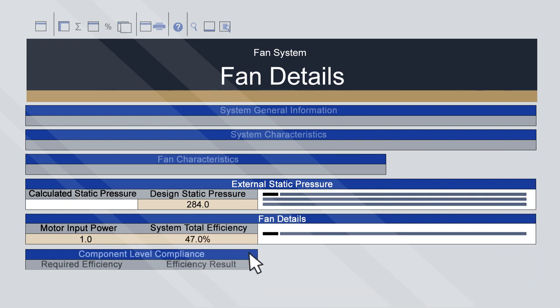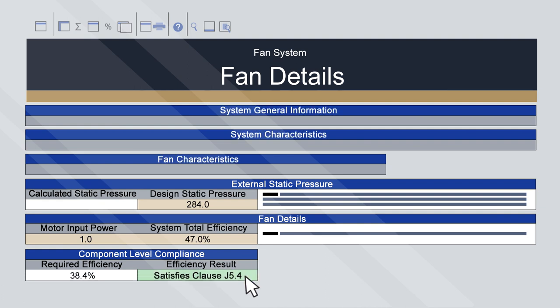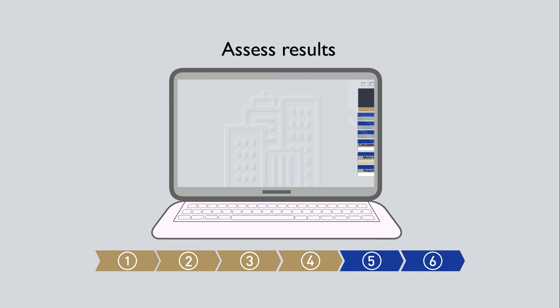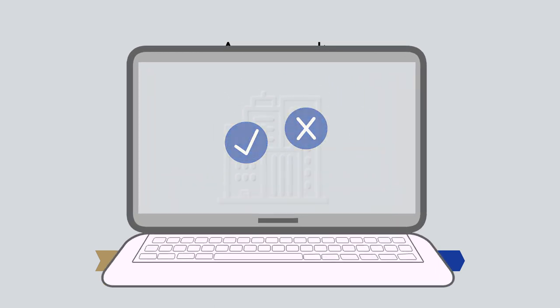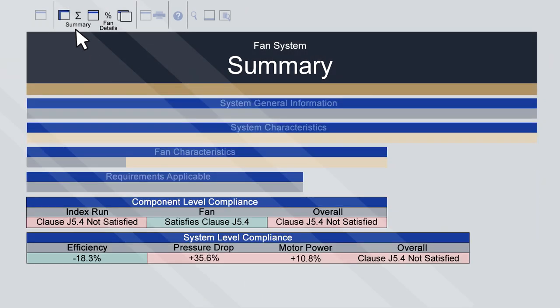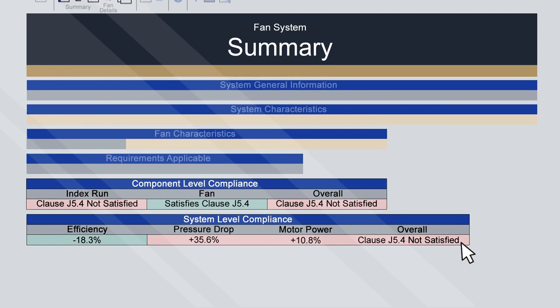The calculator will now determine if the fan satisfies Clause J5.4 at a component level. In this example, it does. Step 5: assess the results. Returning to the Summary sheet, the results at the system level are shown. This system doesn't satisfy Clause J5.4 and requires better energy efficiency.